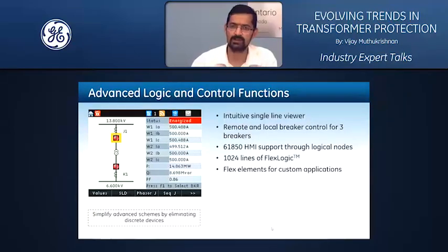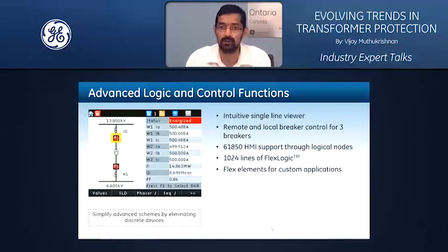So the single line diagram with summary information is step one. Then you should be able to control the breaker either locally, through breaker selection and open/trip breakers, or remotely. Up to 3 breaker control functionalities for a 3-winding application would be a real add-on value for a transformer protection relay. In a 61850 system, completely integrating into your HMI through logical nodes for measurements and interlock will be the next level of control you can accomplish.